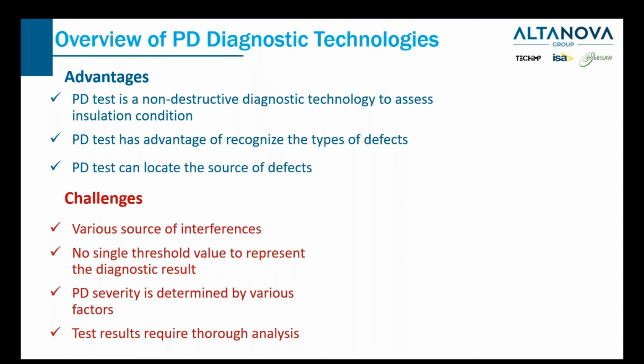So again, the dielectric loss is very effective to tell the overall performance of a cable system, but it cannot distinguish, for example, if I have a large water tree or another cable with thousands of small water trees, the tan delta value will be the same. I cannot differentiate these two scenarios. The benefit of using PD test is if there are multiple discharge activities, we can recognize them. We can do the analysis on each individual defect and perform the evaluation or the trending analysis for each individual defect. Therefore, we can give specific suggestions or action items on each individual defect. So this is a great advantage of using partial discharge testing technology.